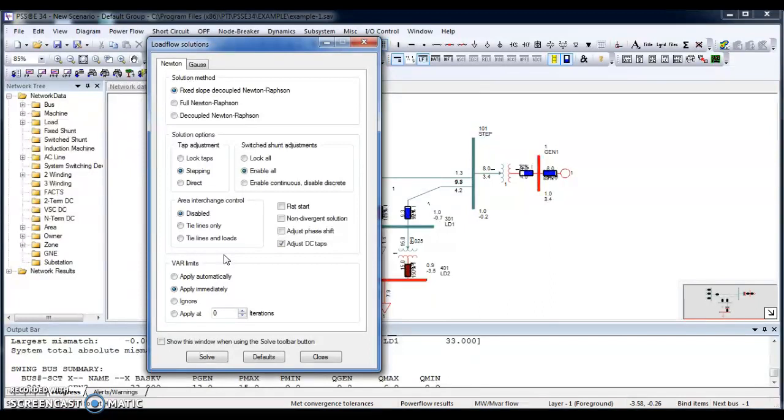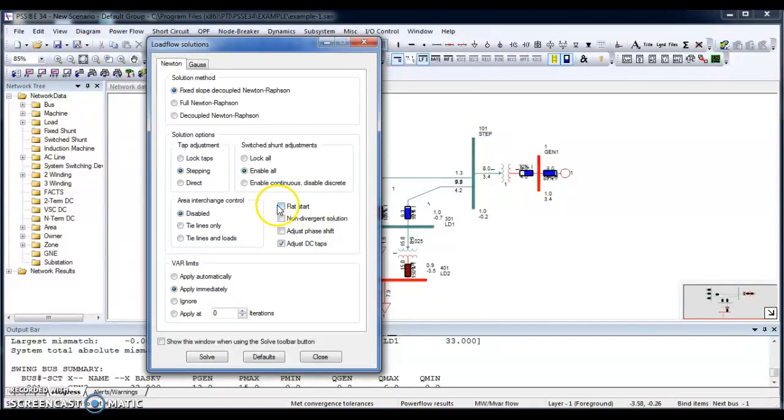And on your right side, there is a flat start. If you select the flat start, it will start your iteration from zero. If you don't select this flat start, it will start your iteration from the previous results, so it will make your solution in a fast pace.